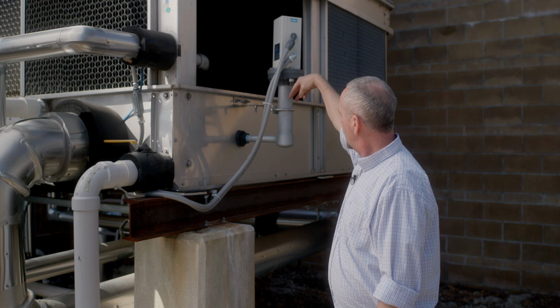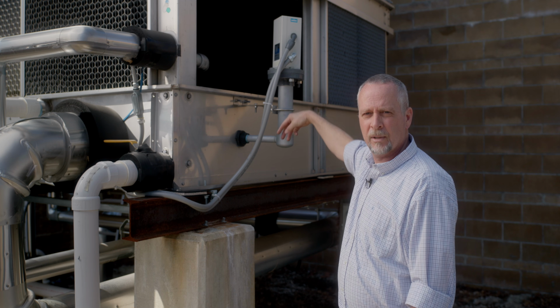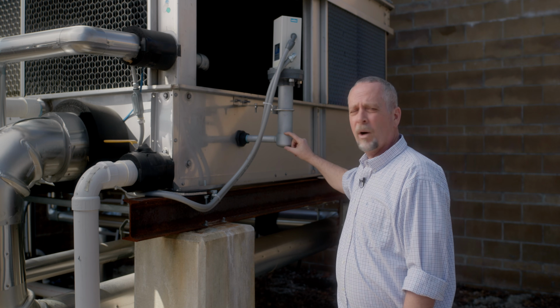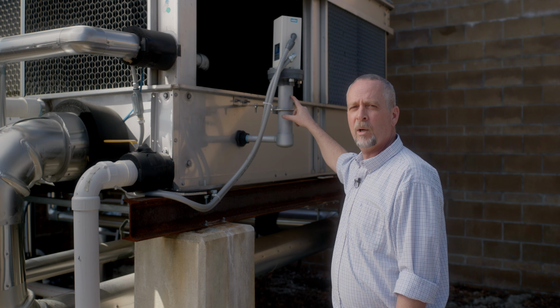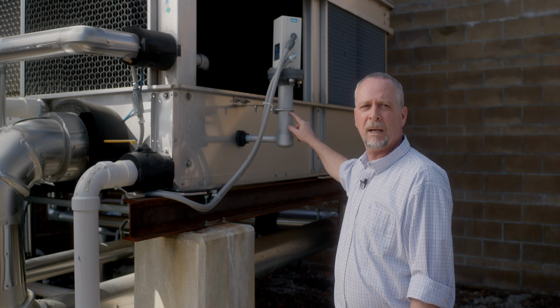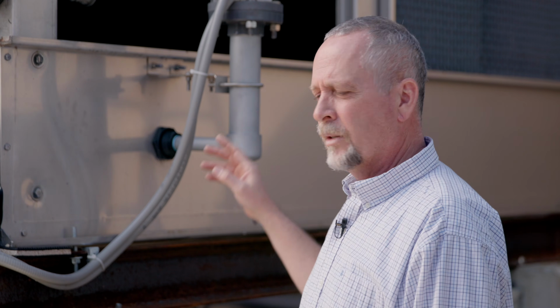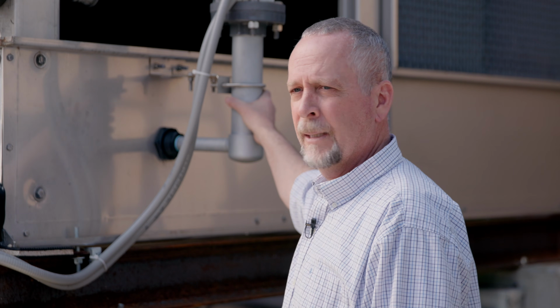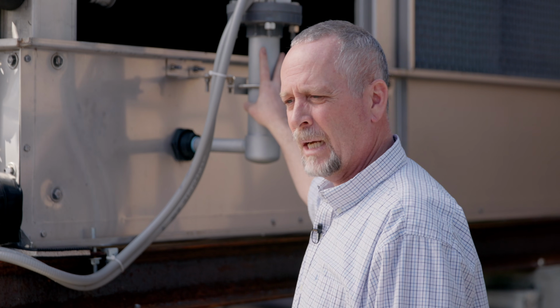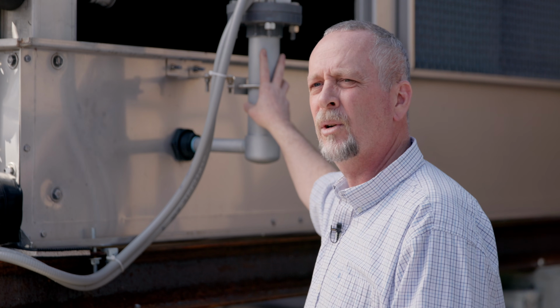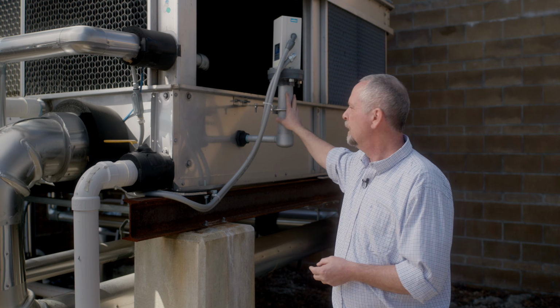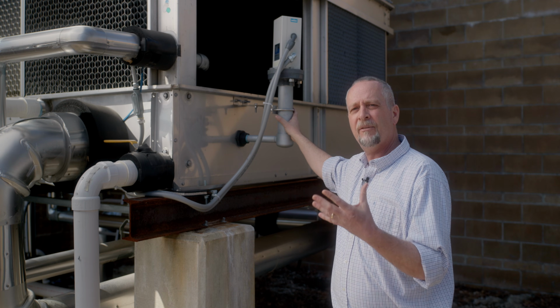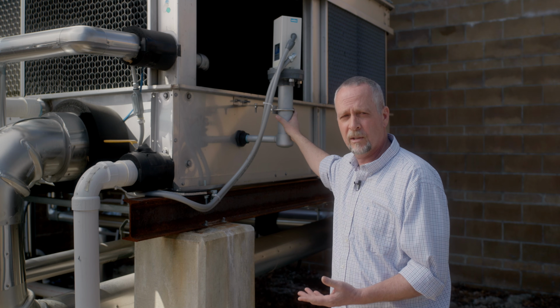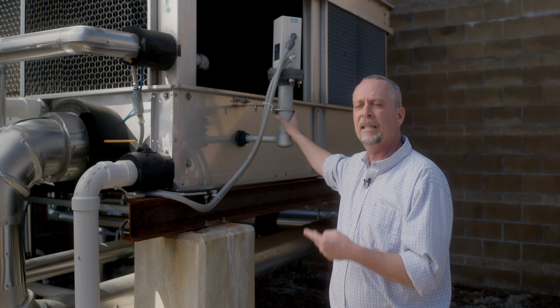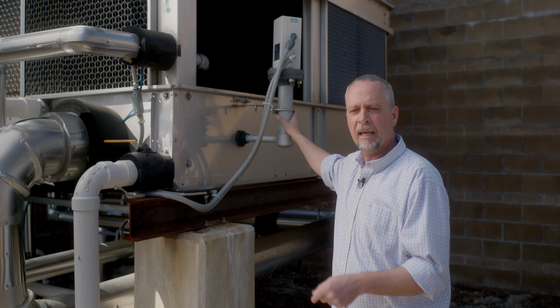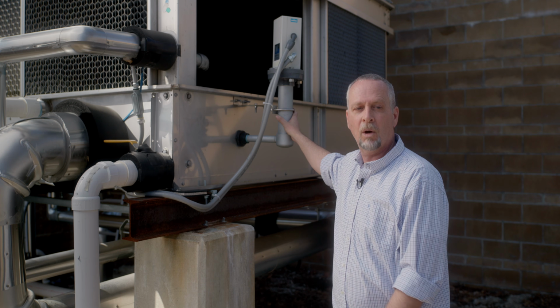Well, down in here, I've got 3 electronic probes. One probe tells me my water needs to fill. The other probe tells me my water's too high, and the center probe is where my water needs to be at. So you got 3 probes there. There's also what's called a 5 probe. Does the same function as this one, except it has 2 additional probes, and those are alarm points for a building management system. So if you ever open one of these guys up and you see 5 probes, they may or may not be using those other 2 probes, but 2 of them are dedicated to generate an alarm to the building management system saying my cooling tower is low on water.